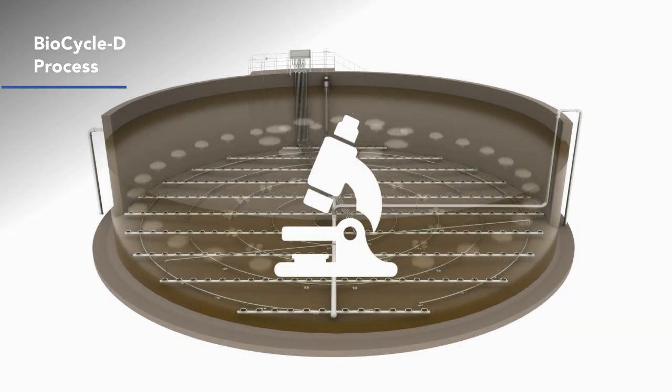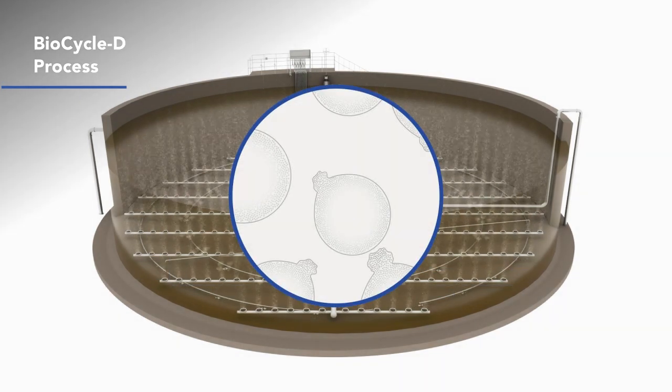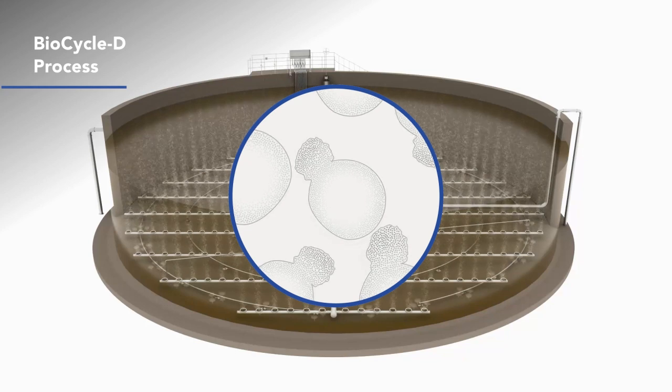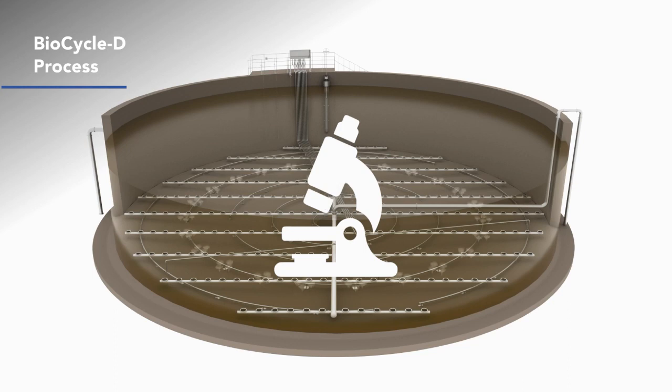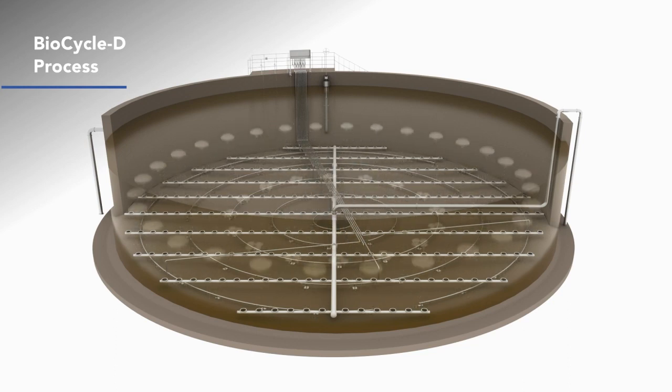Cycling air on and off causes cell walls to rupture, which allows for increased volatile solids destruction and improved sludge dewaterability, reducing polymer consumption. The system continues to alternate between aerobic and anoxic cycles.